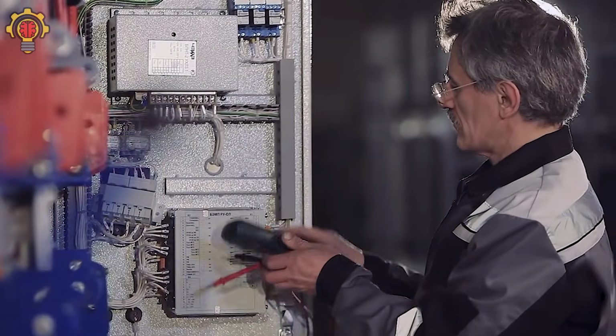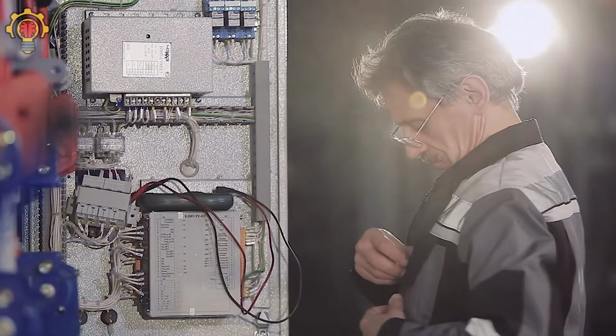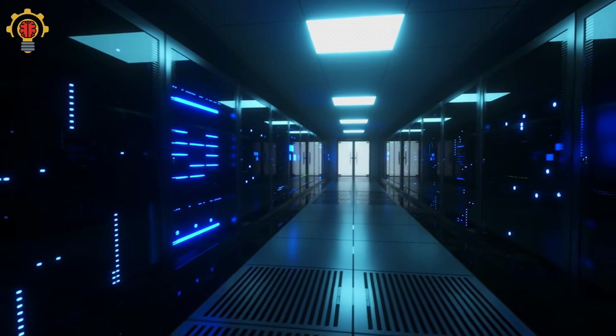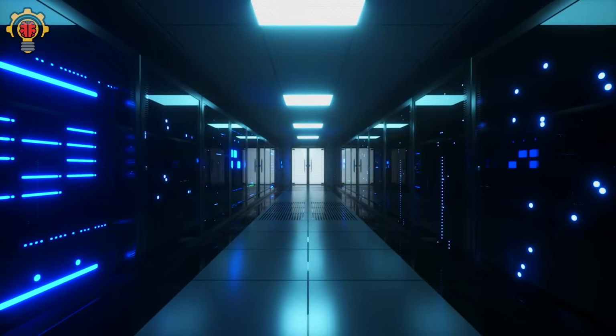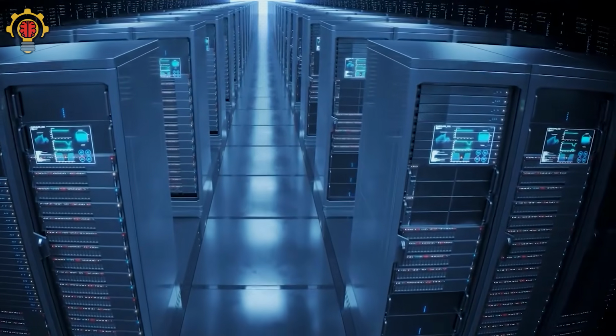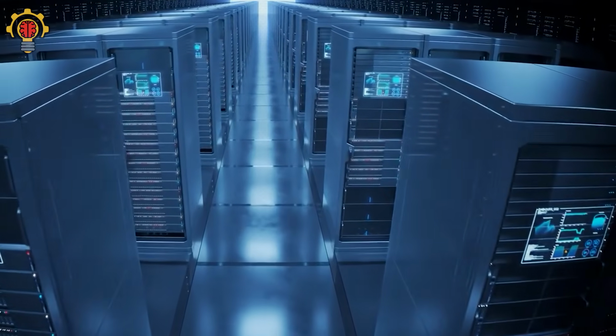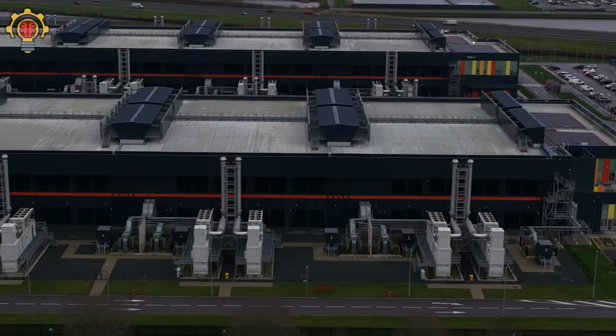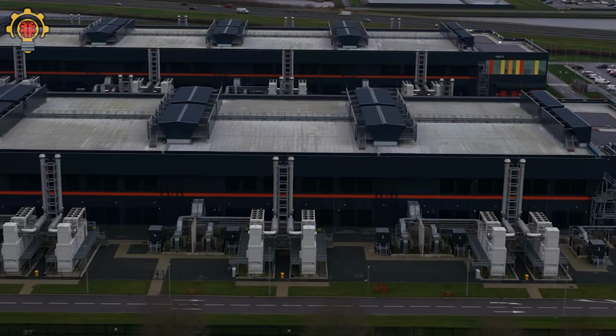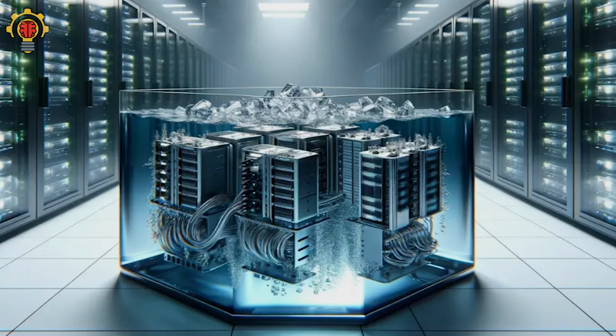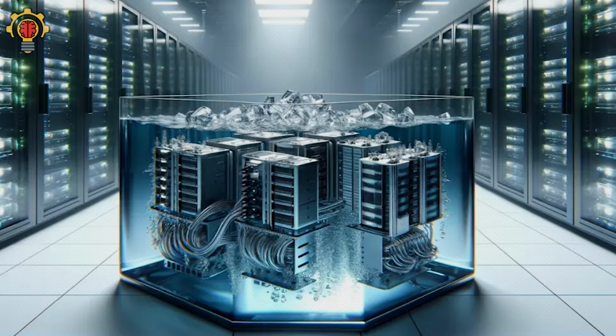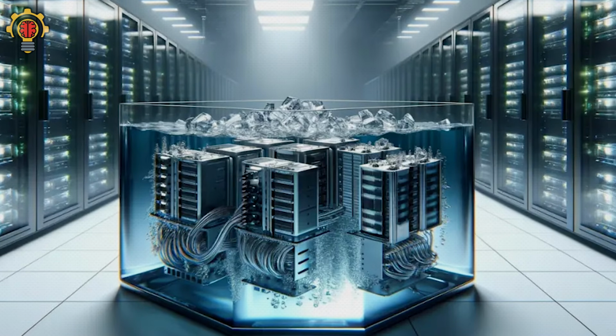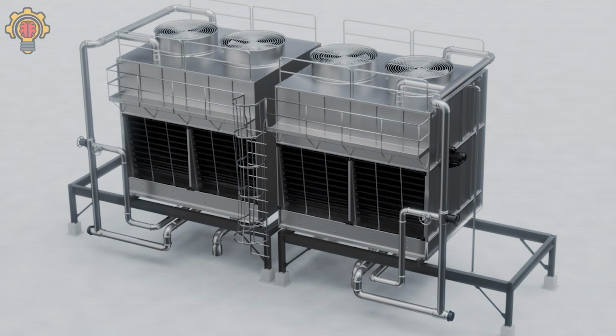instead of placing server racks directly on the building floor. The entire data center floor is elevated several inches above the structure underneath, sometimes 6 inches, sometimes 30 inches. That empty space below becomes a giant air chamber called an underfloor plenum. Cold air is pumped beneath the floor, then released upward through perforated floor tiles placed only where cooling is needed.